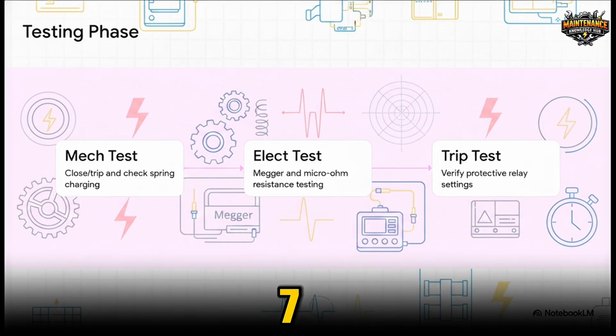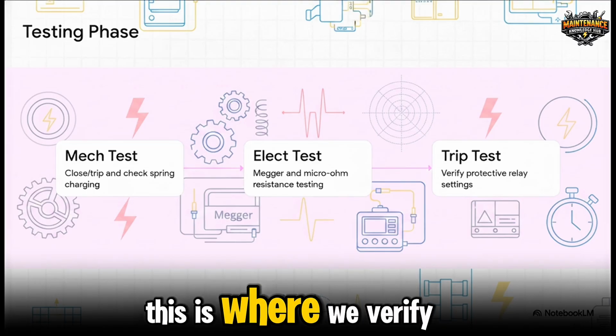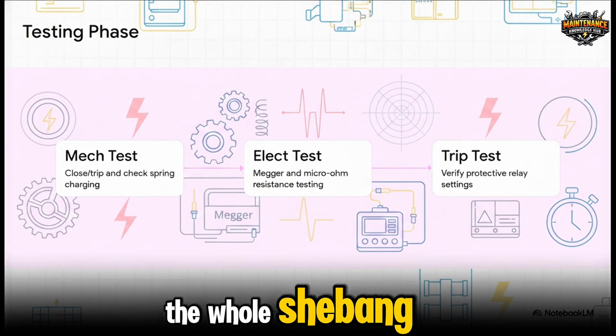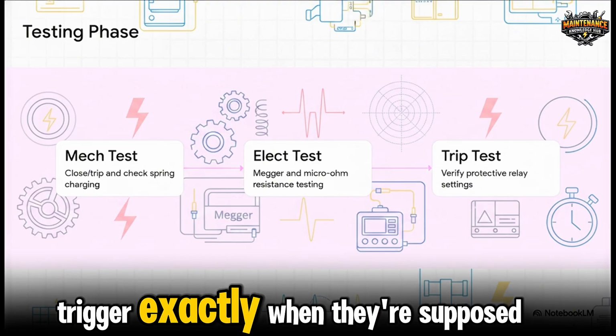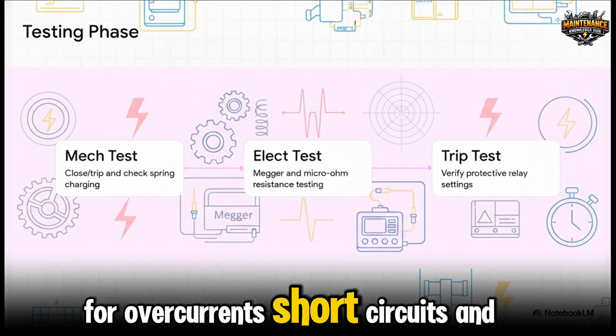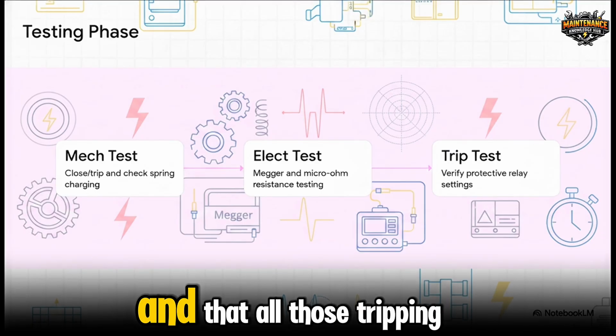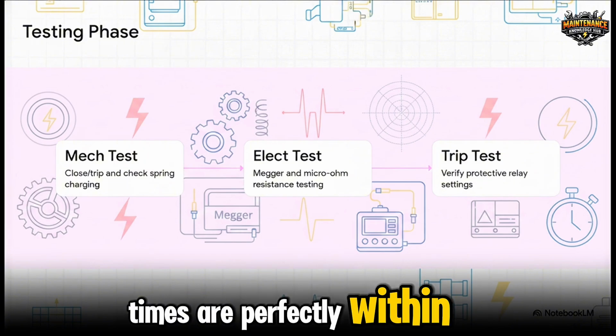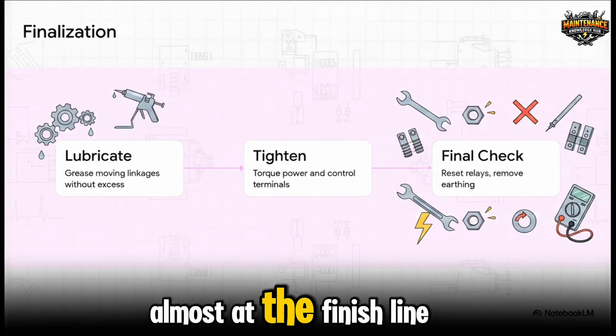Then step 7, the functional trip test. This is where we verify the whole shebang. We guarantee the relays trigger exactly when they're supposed to for overcurrents, short circuits, and earth faults. And that all those tripping times are perfectly within spec. Almost at the finish line now.